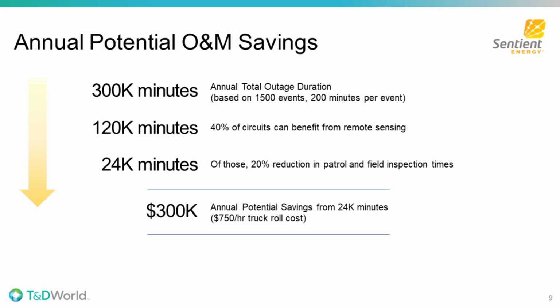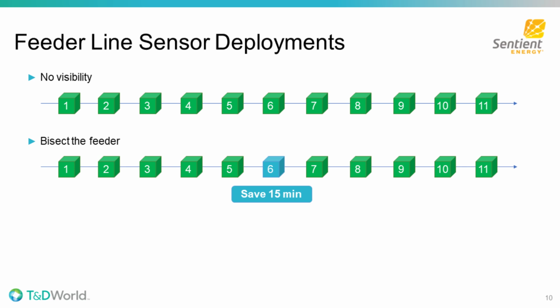Over to you, Stephen. Okay, thanks, Videsh. So let's talk about line sensor deployments and how they save time for crews as they search for underground faults. The top graphic represents a simple radial feeder with 11 switch cabinets and no remote visibility. In the graphic below, we've created visibility at the midpoint, at 6, with a 3-phase line sensor. With this sensor, we've essentially automated an early step in the crew's fault finding process, checking the midpoint, or checking cabinet 6. By automating this step, we save the crew about 15 minutes, and they can jump ahead to the next step in their process.